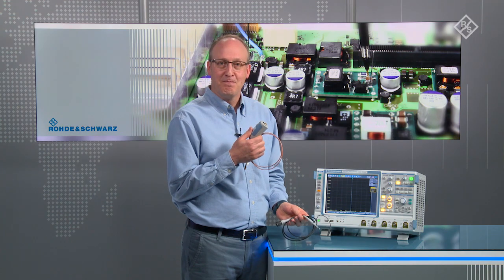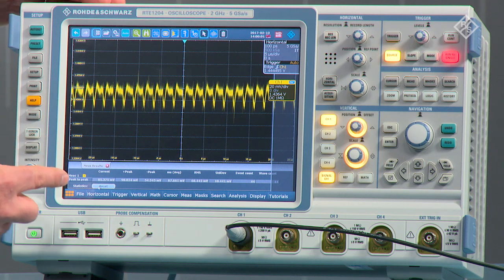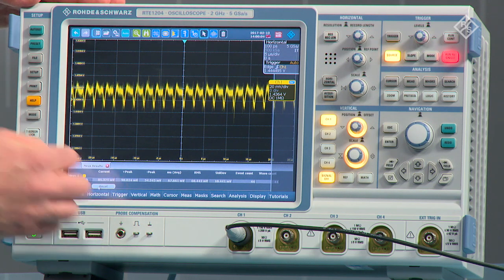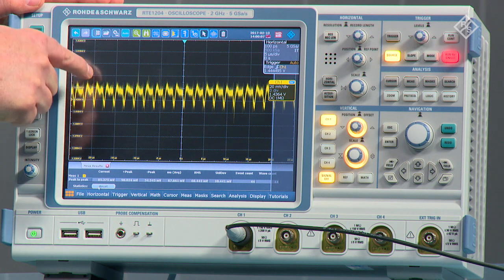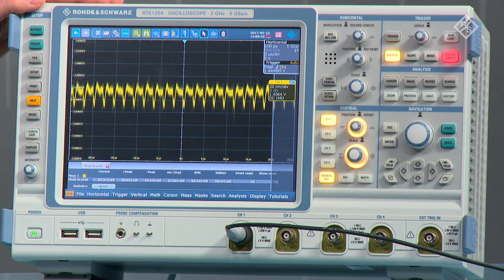Third, use the right probe for the job. How much difference does a probe make? It's huge. Let's look at a comparison between 2 probes. We're going to take some measurements using a 10-to-1 passive probe, and then we're going to take some measurements using the ZPR20 that has been specifically designed for power rail measurements. For my first measurement, I'm going to use a 10-to-1 passive probe. Probes that have higher attenuation ratios amplify noise, and poor grounding can also impact measurements. In this case, we've taken a measurement that's almost about 100 millivolts peak to peak. And if you look at the signal on the screen, you can see significant noise in the waveform.